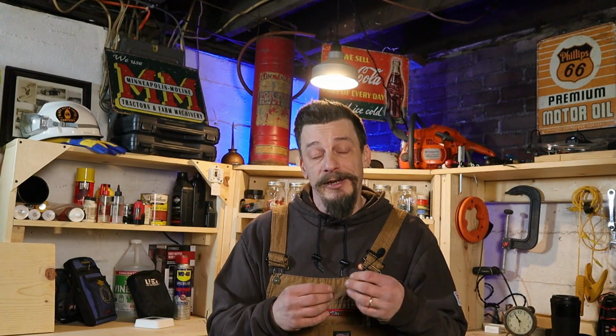Now, all heating and air conditioning systems have a transformer somewhere in that system. So whether we're talking about boilers, furnaces, air conditioners, there is a transformer that takes high voltage coming into the main unit and steps it down to 24 volts. And that 24 volts is always fed to these R terminals. So if we're talking about an R terminal on a control board, R terminal on the thermostat, even R terminals on defrost control boards and heat pump systems, that R terminal is receiving 24 volts from a transformer, and this is the voltage that is the beginning of all our low voltage control circuits in our system, regardless of what kind of system we're talking about here.